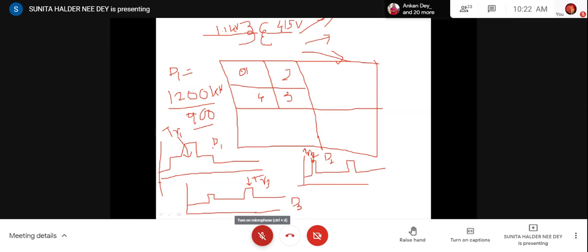Now, say these are not at the same time. Then what will happen? The demand in this area is here, and here it is at another time. Now why did I tell you to make the demand equal? If the demands are equal, even if the times are not the same, the transformer size calculated will be the same, because if the connected load is the same and you are assuming the same demand factor, then maximum demand will be the same. Here we shall assume a flat demand factor for every subblock, so maximum demand will be the same for each subblock. If your connected load is the same, then maximum demand will be the same, and for that reason the transformer size will also come out the same.